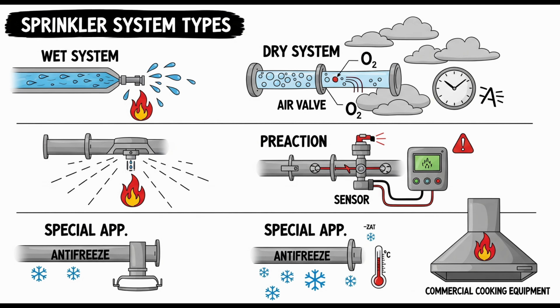Simpler setup. Right. What if one air supply feeds multiple dry pipe systems? In that case, the automatic air supply must be arranged to allow individual maintenance of air pressure for each separate dry pipe system. Each system needs its own dedicated air maintenance device, individual control for each system. Yes. Furthermore, a check valve or other positive backflow prevention device is required in the air supply line to each individual system. And that's to prevent air, or maybe even water if something went wrong, from one system from flowing back into the shared supply and affecting other systems, or air flowing between systems. Exactly. It ensures the independence and integrity of each dry pipe system served by a common supply. You don't want one system's problems impacting another.